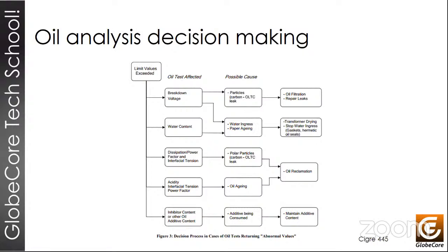Or maybe if we do a little more in-depth analysis, we could determine that the oil has problems with corrosive sulfur and that some additives need to be introduced to prevent the problem from growing, because each of these problems in the oil has different causes, which are now summarized in this table. For example, breakdown voltage can be affected by carbon particles. And one of the causes of carbon particle formation is overheating at some point, or it can be the effect of particles that enter from the outside through leaks, or it may even be caused by tap changers under load, because they can generate particles due to the continuous movement of parts.